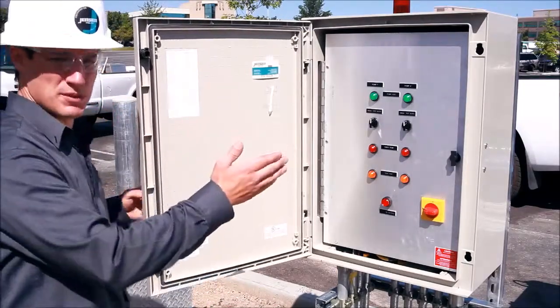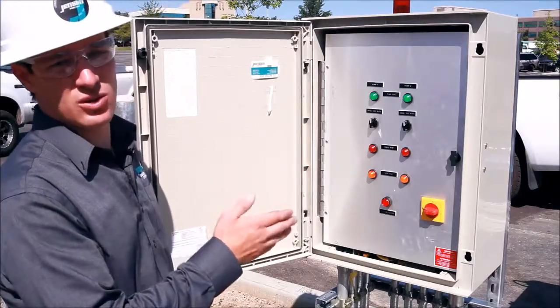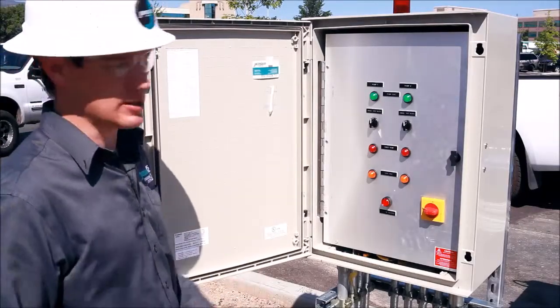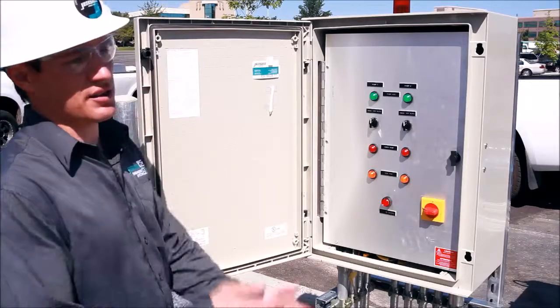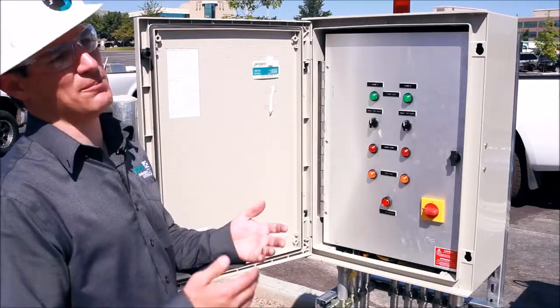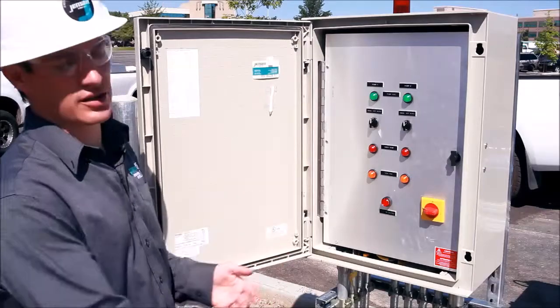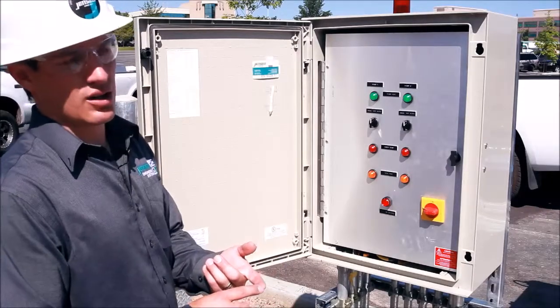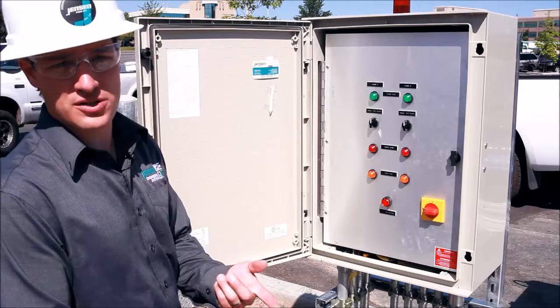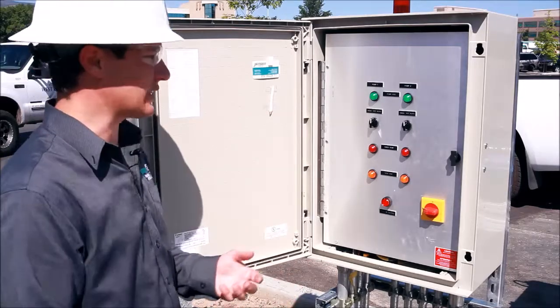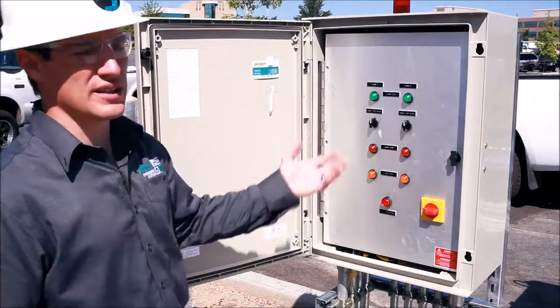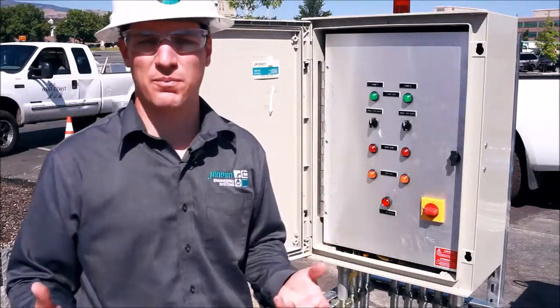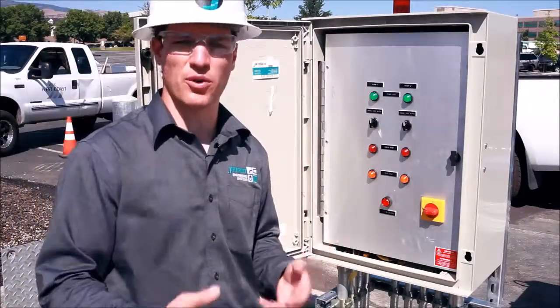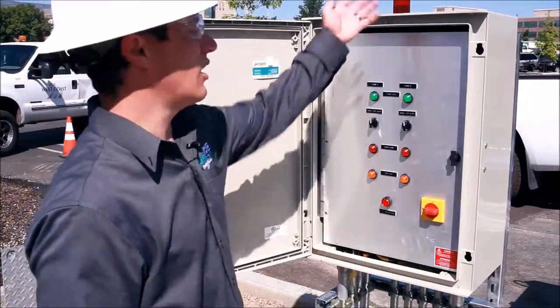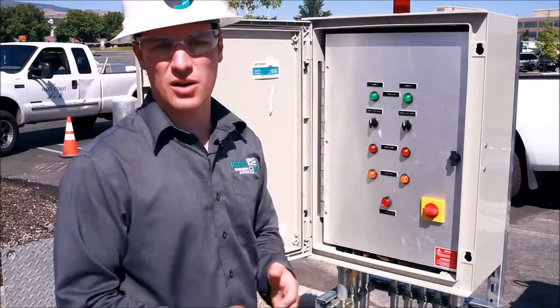Up here, this specific control panel is operated by a Siemens Logo Programmable Logic Controller, PLC. That's the computer. The PLC on this particular model has inputs and outputs. So the inputs are such things as the level of the water from the pressure transducer, the high water float, the low water float, things like that. And then the PLC takes those inputs based on some type of pre-programmed logic, processes those and generates outputs such as pump run, pump turn off, alarm lights, alarm sounds, things like that.